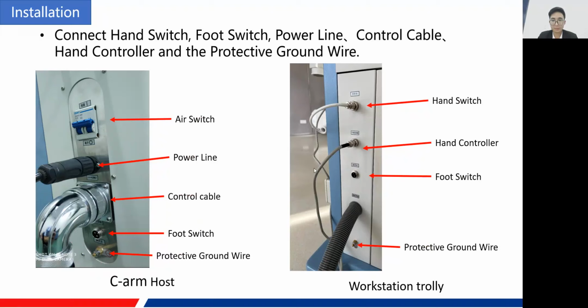So for the workstation trolley, just behind this panel, behind the workstation trolley, you can see the first one, also the hand switch. The second one is for our hand controller. We've got two ports, both in the C-arm host and the workstation trolley, where we can connect our foot switch. You can see here we've got a foot switch port on the workstation trolley too. So you can choose wherever you want to install them. Okay, also the protective ground wire.